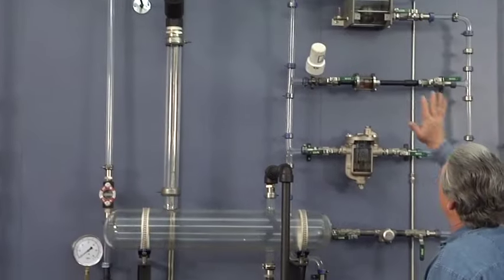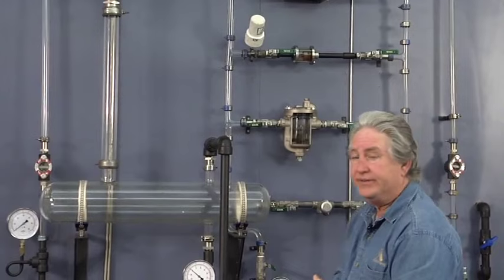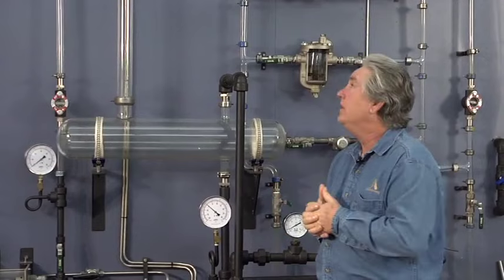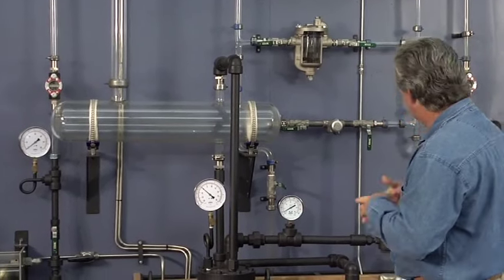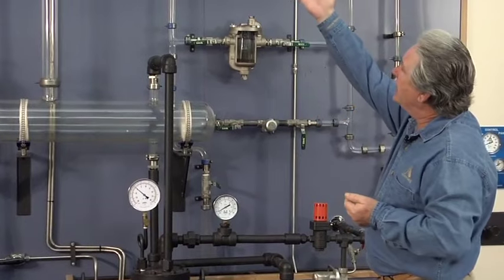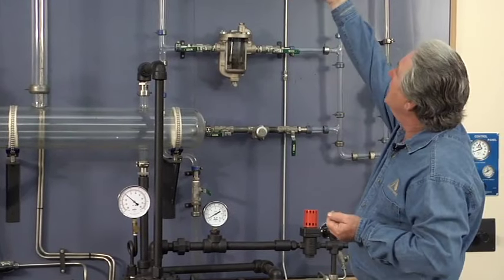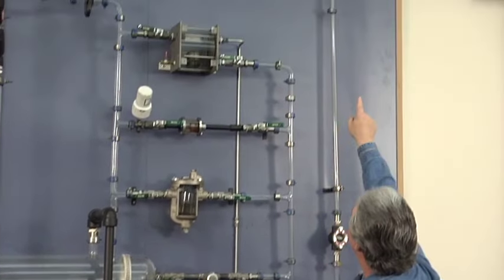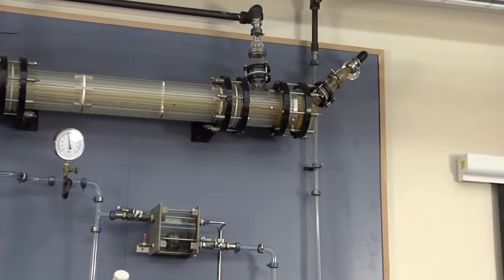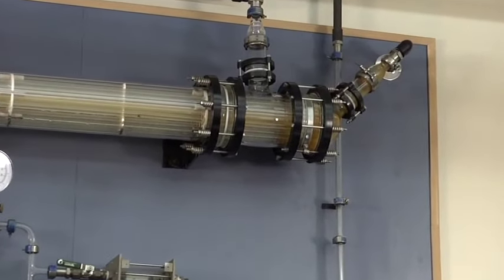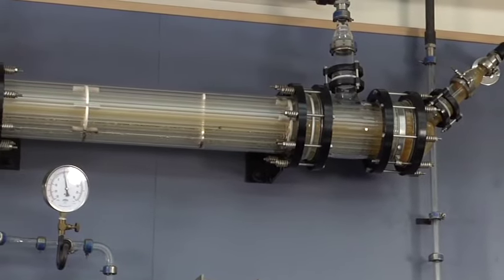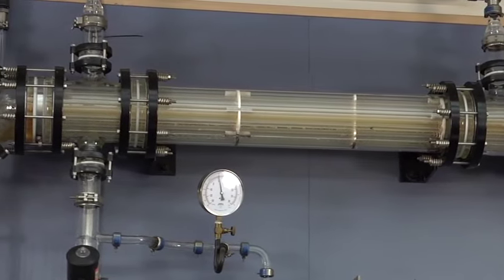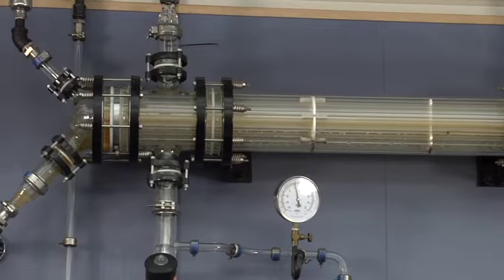Now that we've laid out what our piping arrangement is, let's talk about some of the problems that we commonly incur with exchangers. One is variable flow rates. As we look at what the condensing rate is right now, you can notice that as you see the liquid going through the tubes, there's a continual amount of bubbles that travel through those tubes. That's entrained air in the actual process flow. One reason it's so important to get it out is our ball float air vent on the process side, the 11AV.